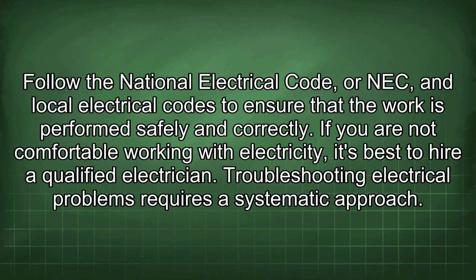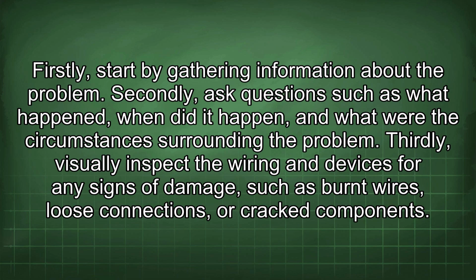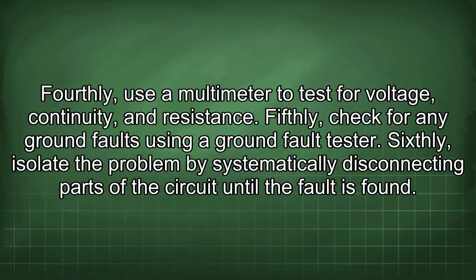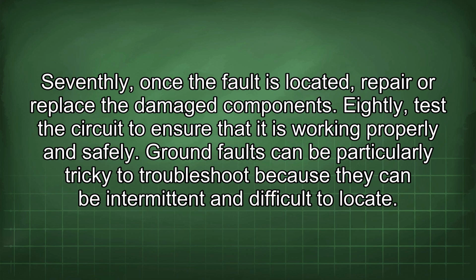Troubleshooting electrical problems requires a systematic approach. Firstly, start by gathering information about the problem. Secondly, ask questions such as what happened, when did it happen, and what were the circumstances surrounding the problem. Thirdly, visually inspect the wiring and devices for any signs of damage, such as burnt wires, loose connections, or cracked components. Fourthly, use a multimeter to test for voltage, continuity, and resistance. Fifthly, check for any ground faults using a ground fault tester. Sixthly, isolate the problem by systematically disconnecting parts of the circuit until the fault is found. Seventhly, once the fault is located, repair or replace the damaged components. Eighthly, test the circuit to ensure that it is working properly and safely.